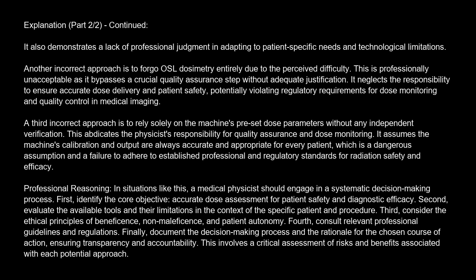A third incorrect approach is to rely solely on the machine's preset dose parameters without any independent verification. This abdicates the physicist's responsibility for quality assurance and dose monitoring. It assumes the machine's calibration and output are always accurate and appropriate for every patient, which is a dangerous assumption, and a failure to adhere to established professional and regulatory standards for radiation safety and efficacy.